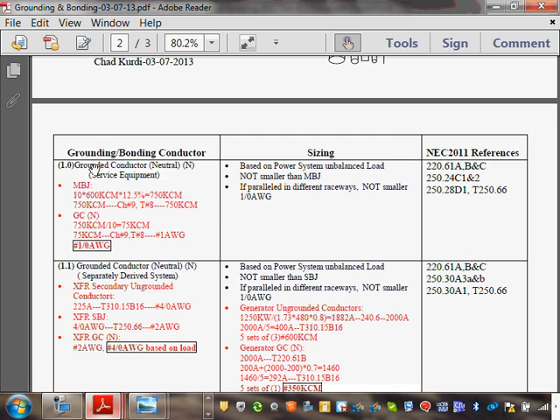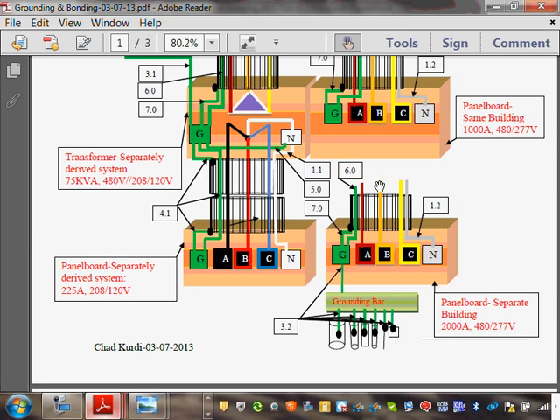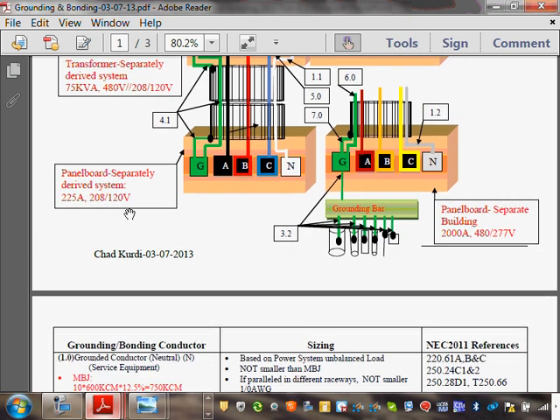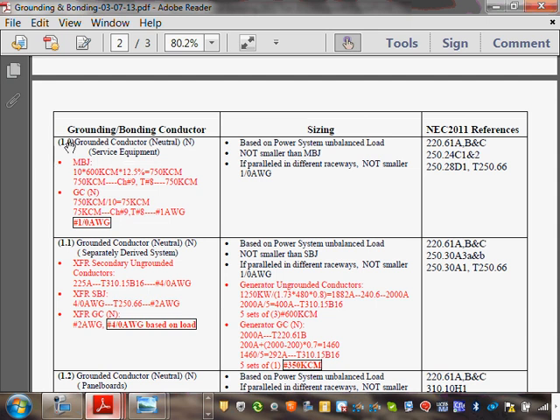What I did is I labeled each and every one of these conductors, which I'm going to walk you through. Can you see 3.1, 6? All these labels are labeled for a reason. Then on the second 2 pages, take each one of these labels and identify what it is. It's called the grounded conductor. It's also the neutral. And where is it? It's at the service. How do we size it? It tells you to size it based on the power system unbalanced load, not smaller than the main bonding jumper. And if you parallel, don't you dare use less than 1/0 if you parallel.